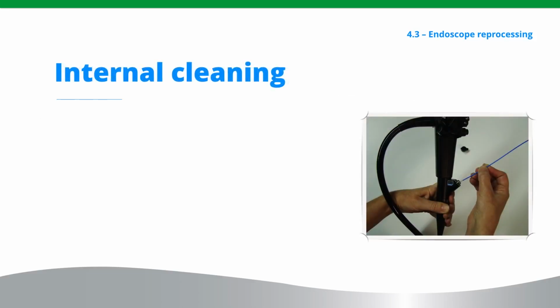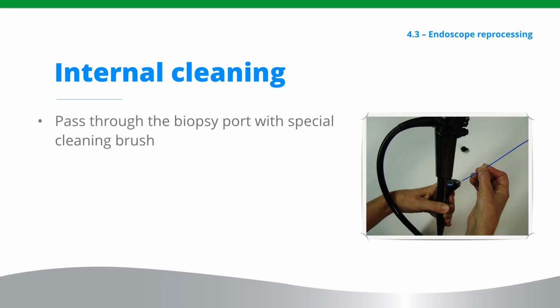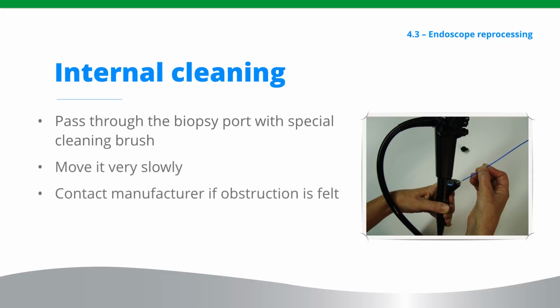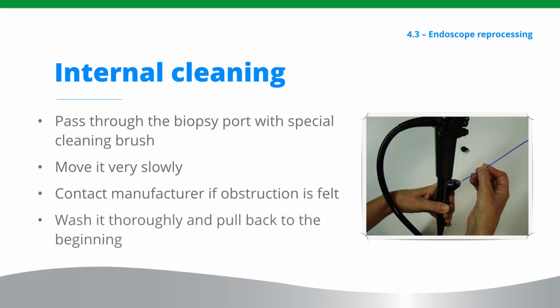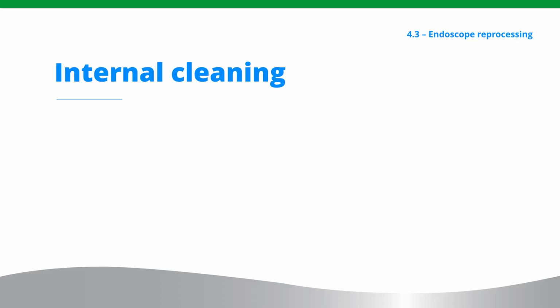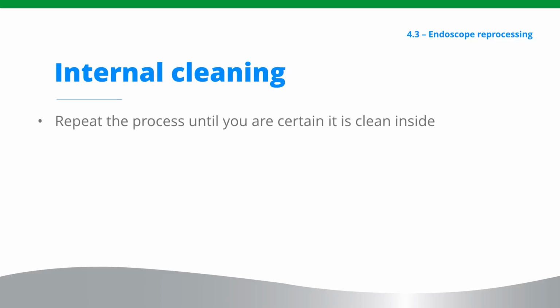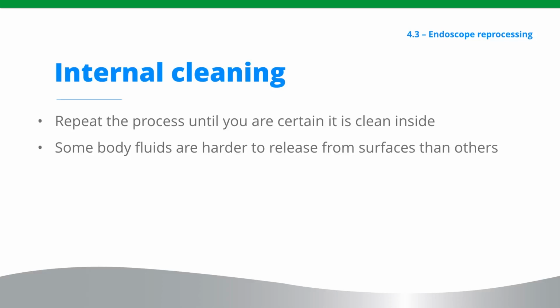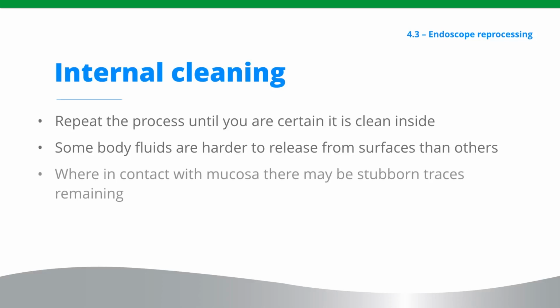After straightening the flexible tip of the endoscope, use the special cleaning brush supplied with the instrument to pass through the biopsy port, moving it very slowly. Contact the manufacturer if an obstruction is felt. When the brush emerges from the tip, wash it thoroughly and pull back to the beginning. Repeat the process until you are certain it is clean inside. Some body fluids are harder to release from surfaces than others. Where an endoscope has been in contact with mucosa, there may be stubborn traces remaining.